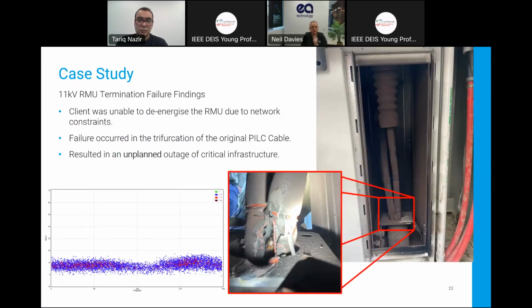the only one we've got in this presentation, really, you've got a distinct cluster just after the 270 degrees, and a distinct cluster here just before the 90 degrees. If this was a single phase event, you would get a distinct hump in the two clusters at 180 degrees separation. The reason we're seeing this quite long clustering here is because we're looking at phase-to-phase type discharge, so more than one phase is involved.